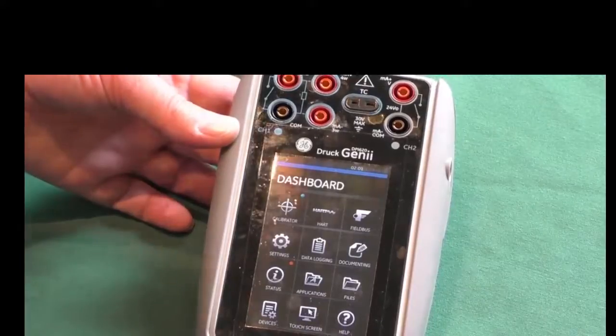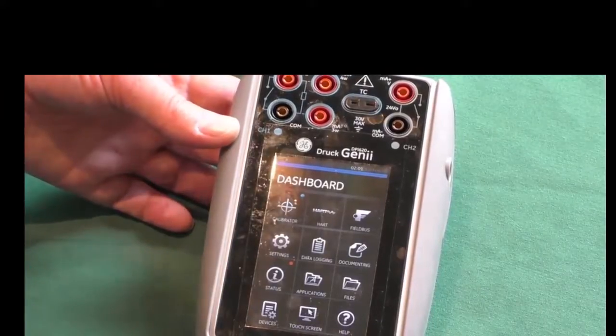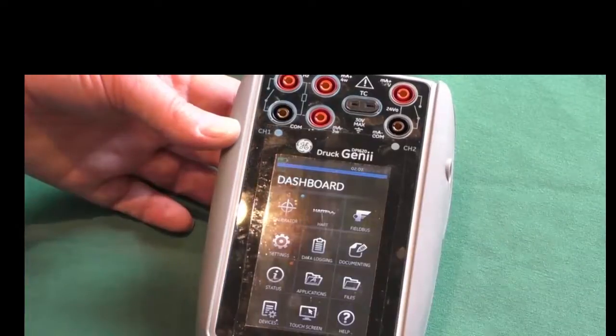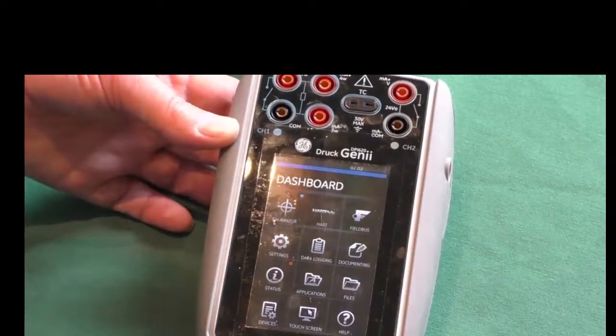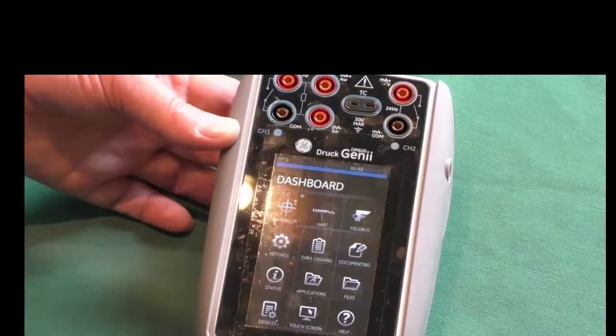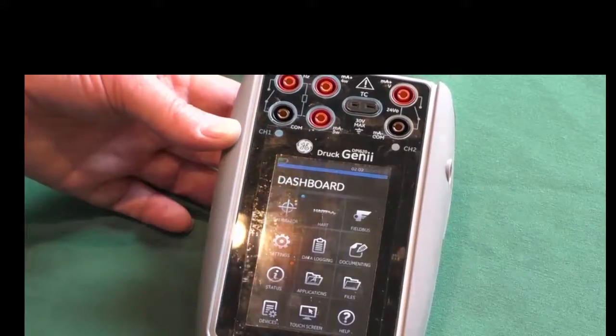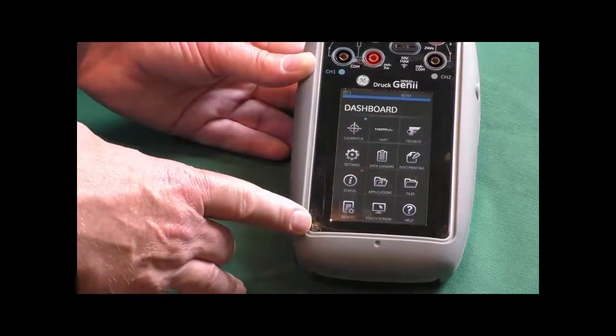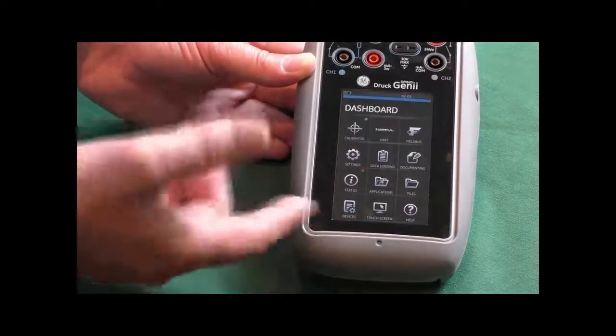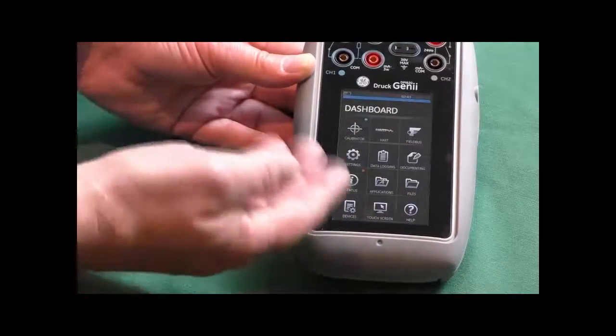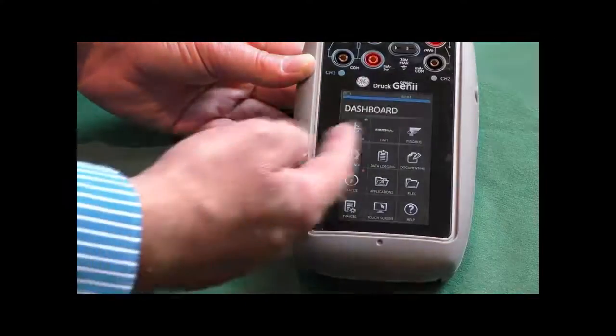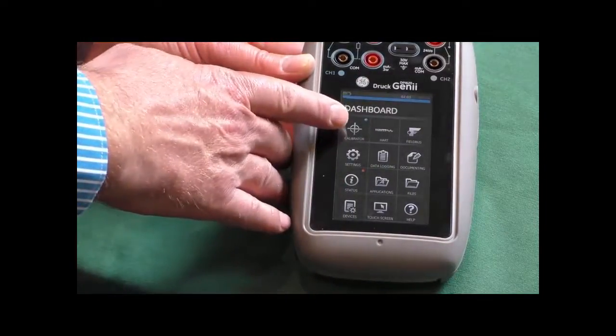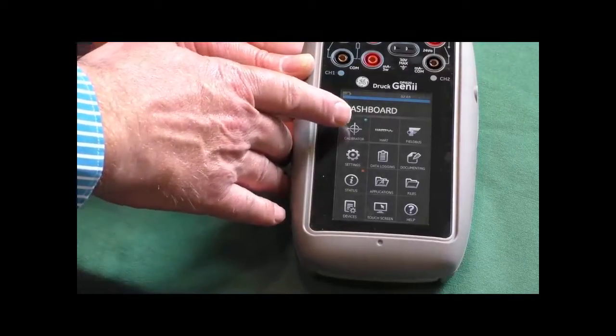Today I'm going to show you quickly how to set up the instrument for an RTD simulation into a transmitter, and so we can set the 4 to 20 milliamps on that transmitter. So the Genii has a capacitive touchscreen, very much like your smartphone which we're all used to, and it's very intuitive. So we have graphics on the front here. As you can see at the moment we've got highlighted the calibrator, which is what I'm going to go into shortly.